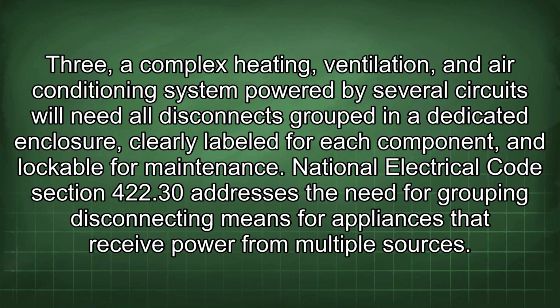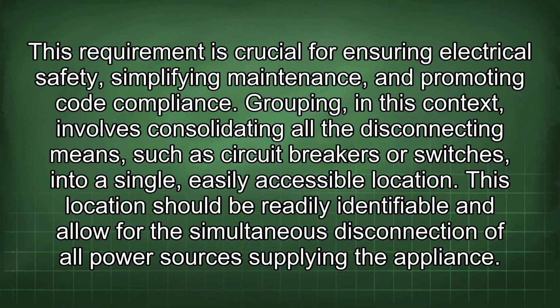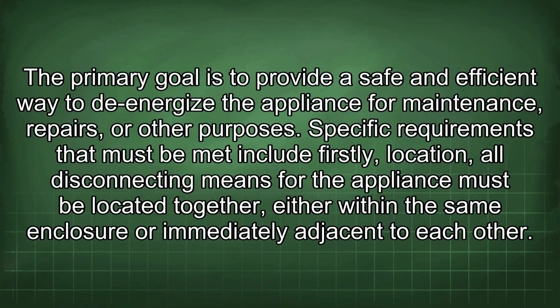National Electrical Code Section 422.30 addresses the need for grouping disconnecting means for appliances that receive power from multiple sources. This requirement is crucial for ensuring electrical safety, simplifying maintenance, and promoting code compliance. Grouping, in this context, involves consolidating all the disconnecting means, such as circuit breakers or switches, into a single, easily accessible location. This location should be readily identifiable and allow for the simultaneous disconnection of all power sources supplying the appliance.